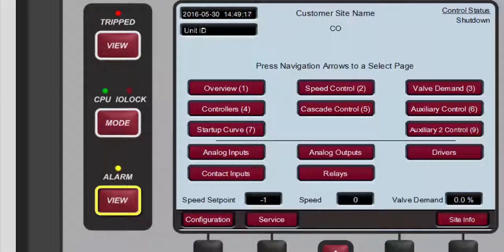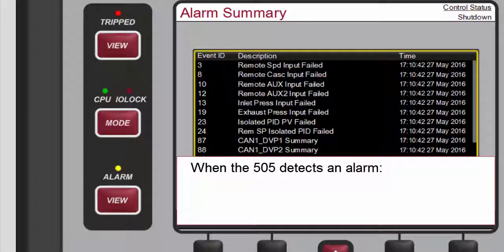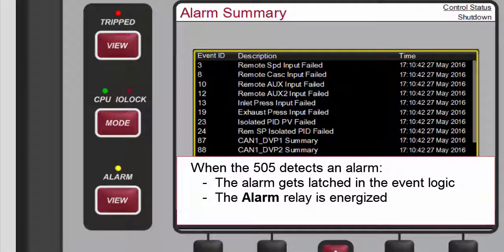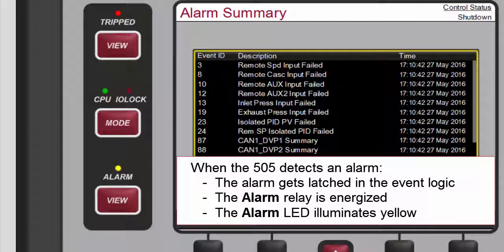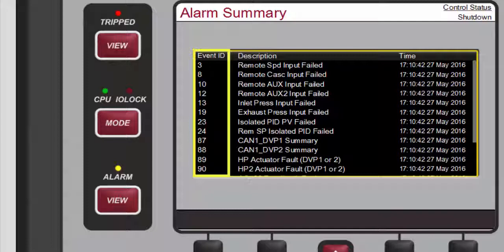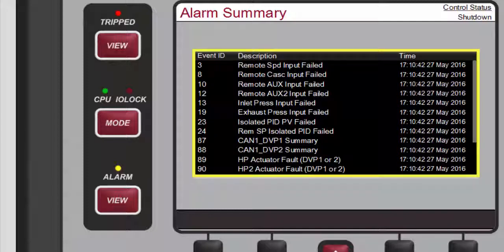Pressing View below the Alarm LED will take you to the alarm summary screen on the LCD display. When an alarm is detected, it gets latched in the event logic, the alarm relay is energized, and the Alarm LED illuminates yellow. The cause of the event will be indicated with an event ID, description, and time and date stamp.